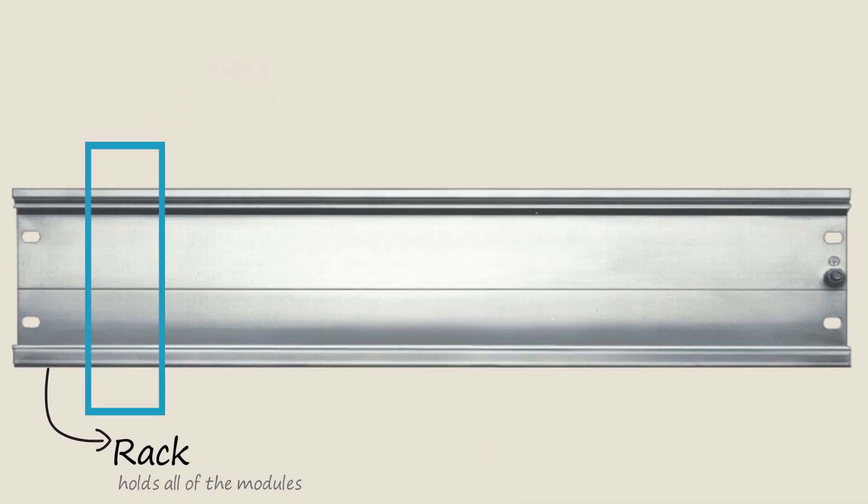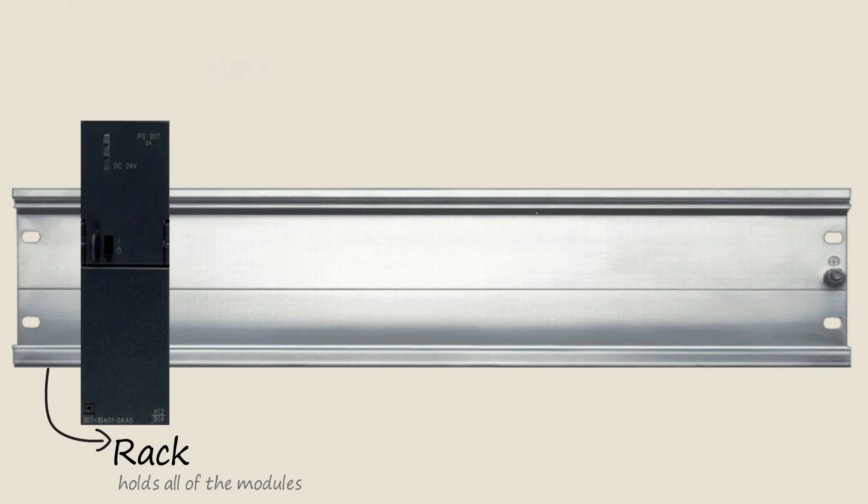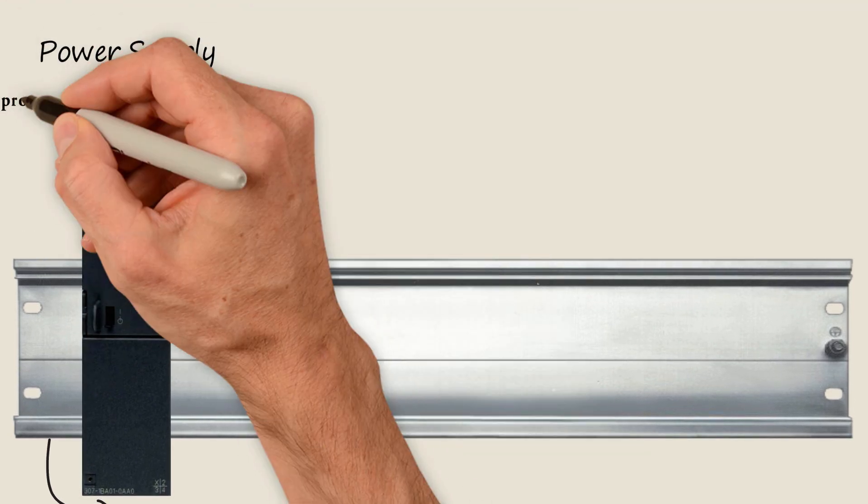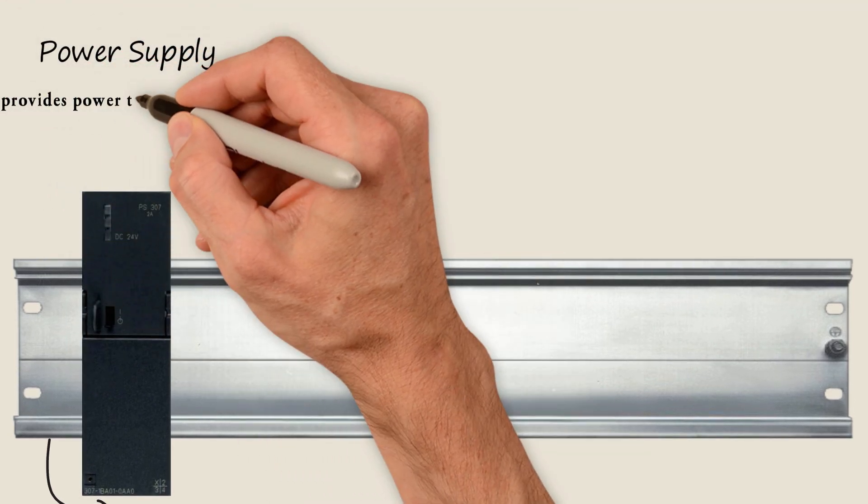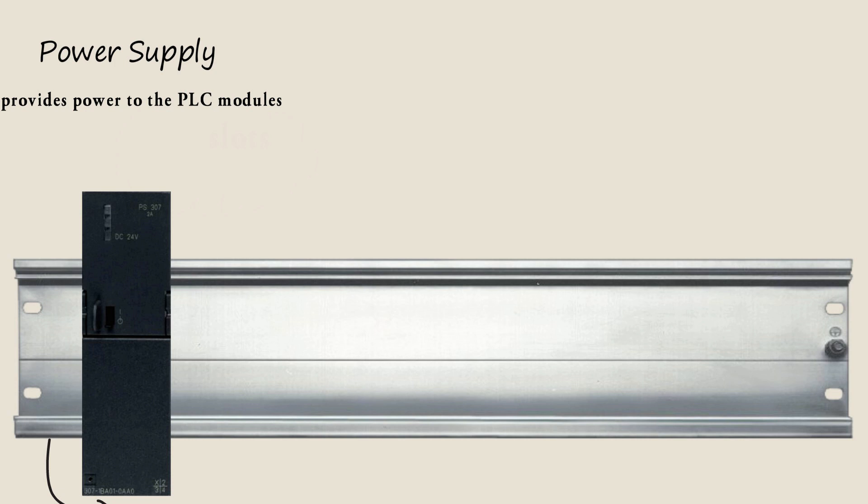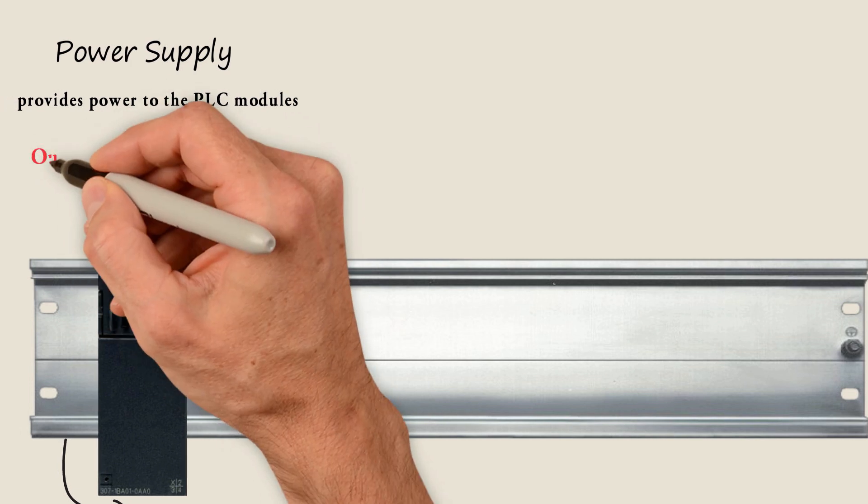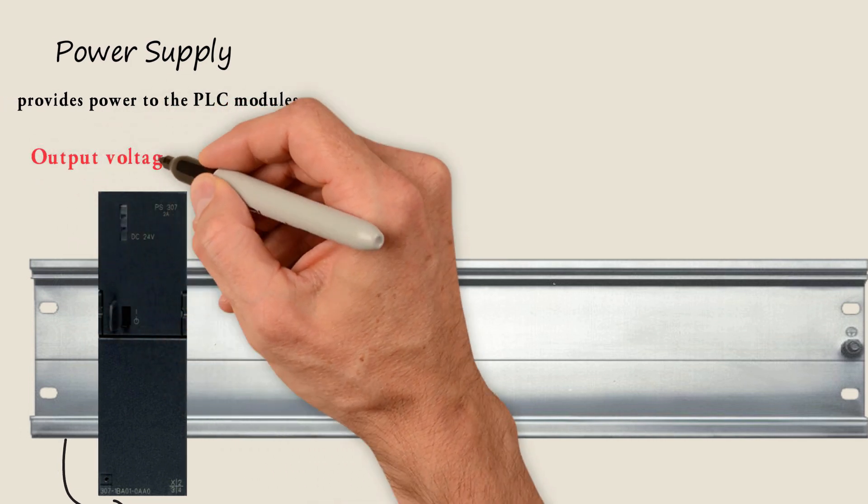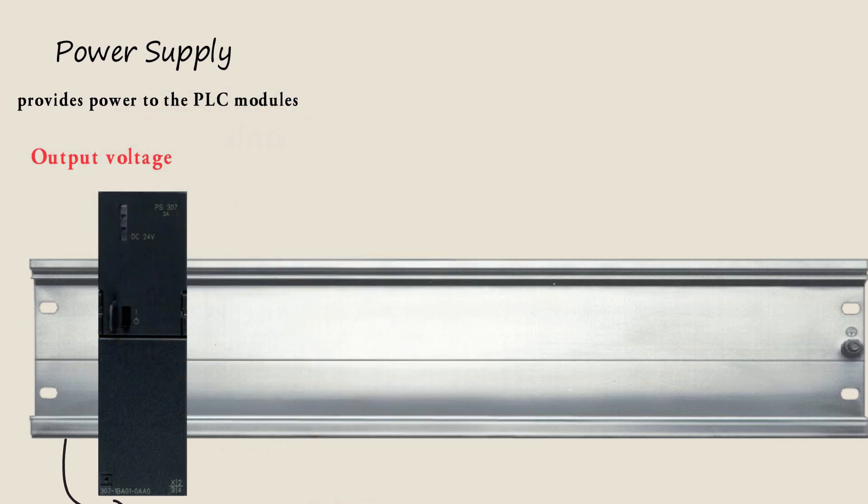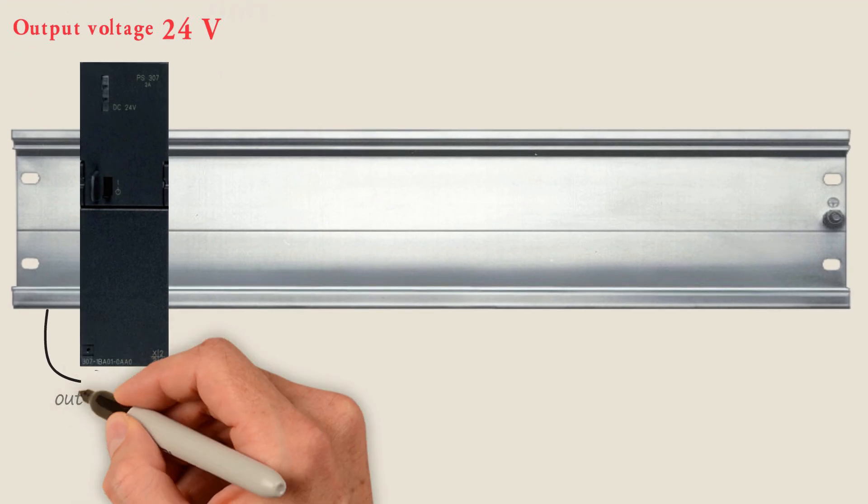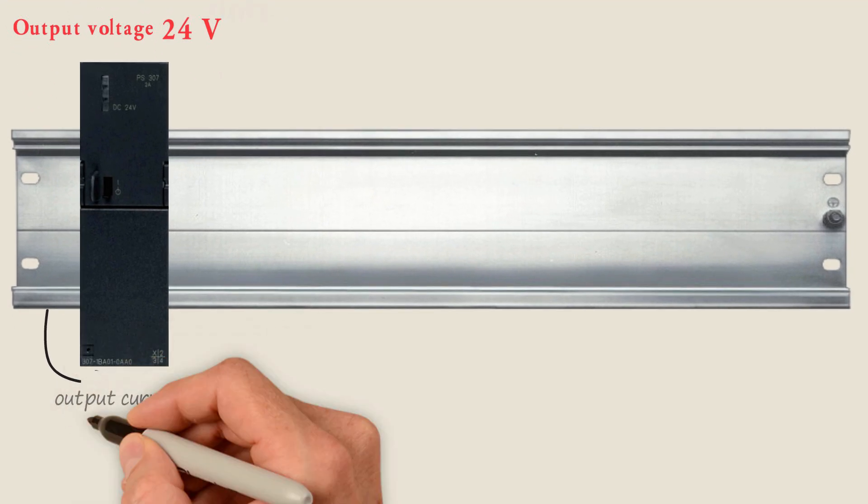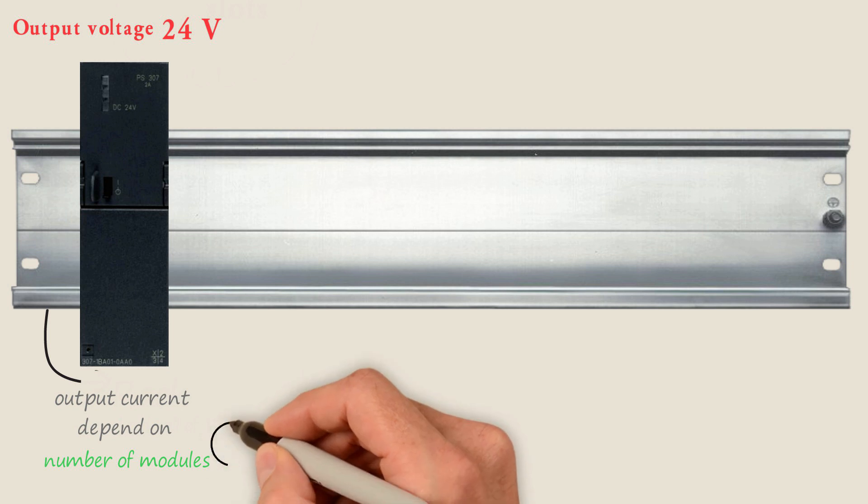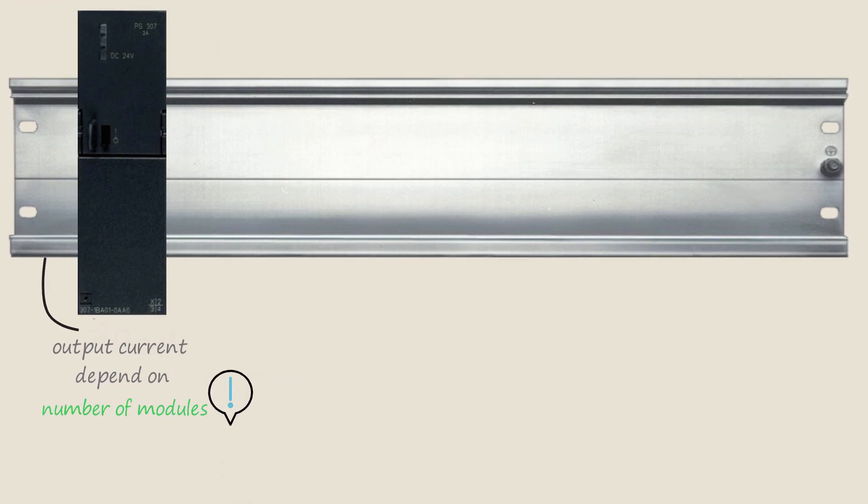The first slot is typically the power supply module which provides the necessary power to the PLC modules. The output voltage of the power supply that we use is usually 24 volts DC, but the output current varies depending on the number of the modules needed in the PLC.